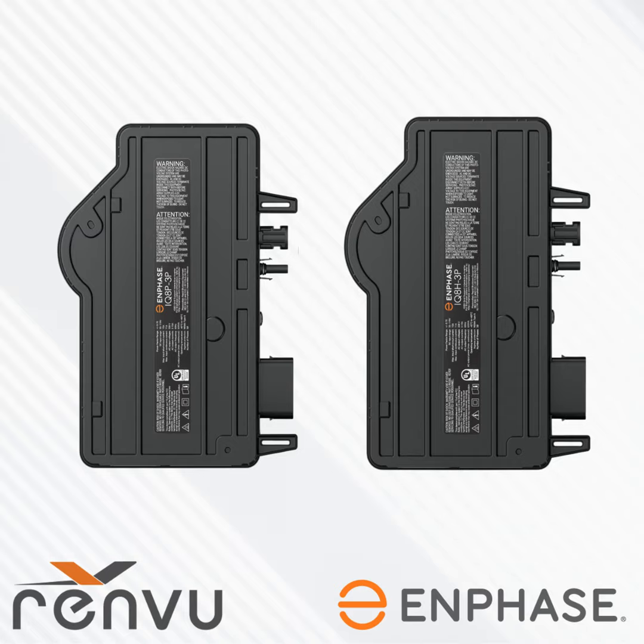Landscape cable is for ballasted arrays or arrays in a traditional landscape orientation relative to the roof, and is meant for modules that have a more common frame format. So if you're dealing with a smaller module in a landscape format, your microinverters are still quite far away from each other, right? Because now we're putting some distance between them. So we need a cable where the drops are actually farther away from one another so that they can reach their corresponding microinverter. Now, if you're using landscape orientation, east-west array maybe, with a giant frame format, you're going to want to step up to that longer landscape cable, and that's its intended use. So the spacing's 9.5 feet apart.